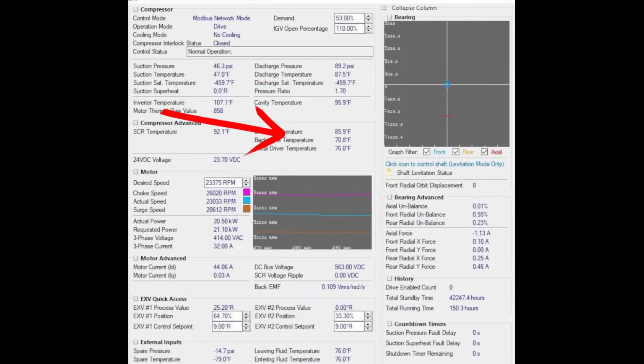The ratio between these two gives us where we're at in our surge curve, which is the lift compared to the flow. Now, another way to say flow is speed. So speed is another term we could use instead of saying flow. Now, the reason that the surge is lower is because these set points are dictated based off of this ratio. So as this ratio increases, these speed thresholds will increase. And as this ratio decreases, these speed thresholds will decrease. And so this will be a constantly fluctuating point based off of this pressure ratio.